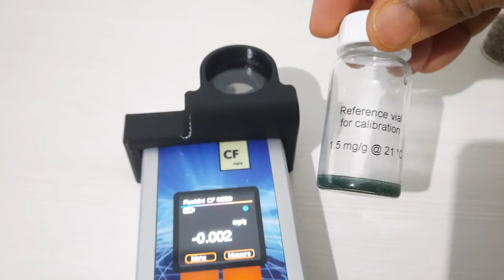So now I will put the sample vial here. It is the reference vial, so it should give a reading in the 1.5 range. So I will just measure it again. It is giving 1.6. We need to calibrate it, so I will try to calibrate it again.